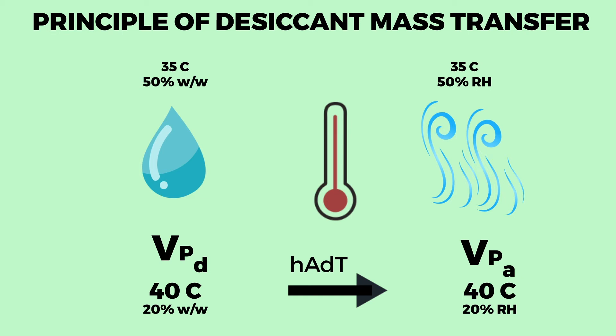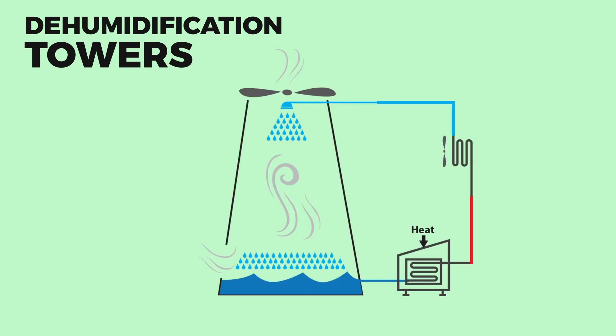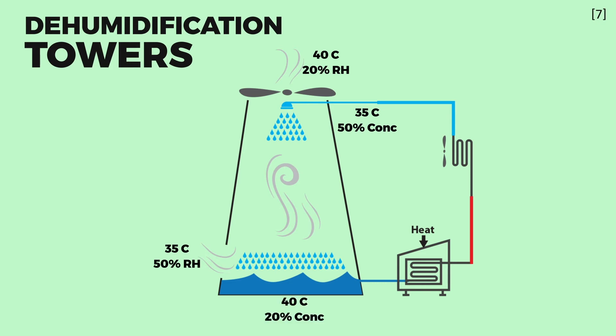Now we know exactly what happens when a desiccant solution comes in contact with air and how it dehumidifies, and as a side effect heats air as well. Common practical uses of desiccant-based dehumidification involve dehumidification towers. A chilled concentrated solution is sprayed at the top of the tower and interacted with air. The air leaves at a slightly higher temperature but drastically reduced humidity, while the desiccant solution leaves at a high temperature and low concentration — essentially diluted. This solution then has to be regenerated and cooled by removing the absorbed moisture and generated heat.